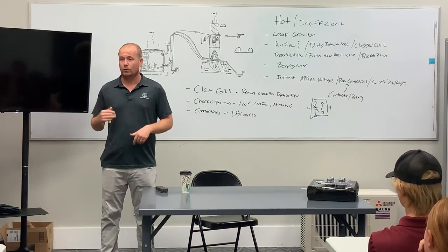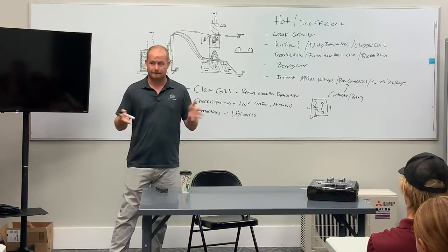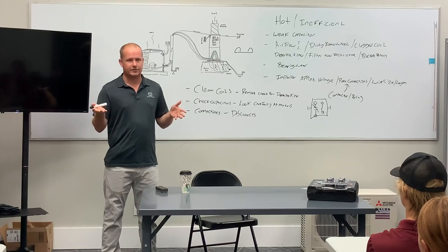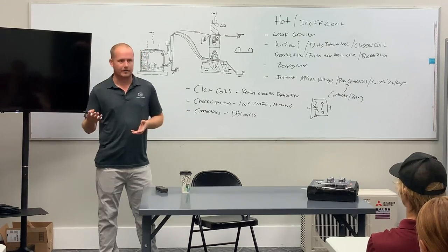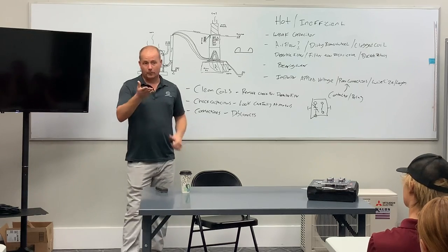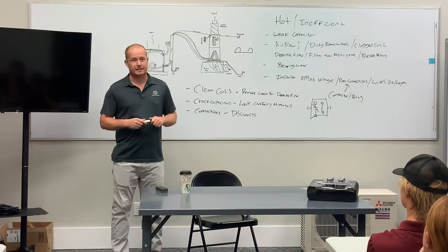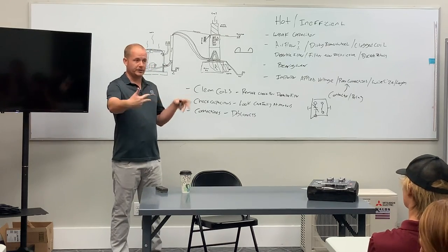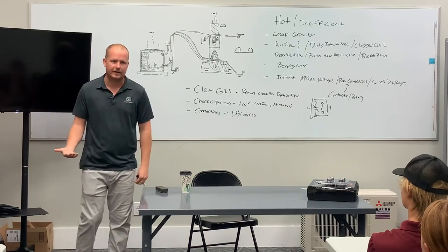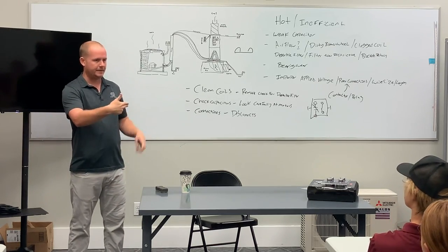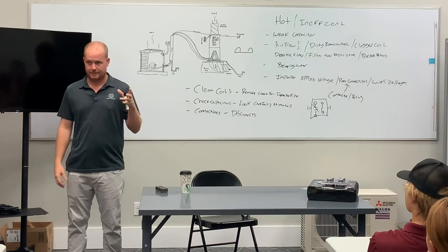Now, when they are pulling off the wall, that can cause a real problem. And what is the real problem that it can cause? Anybody know? Safety hazard. What's a safety hazard? Sure, a short, because it's flopping around in the breeze. It can fill up with water, that's the main reason. That's the one I was looking for. Because in a lot of cases, the high voltage conductors are coming in the back of the disconnect. And if that's pulling off the wall, now there are openings in the back of that disconnect.